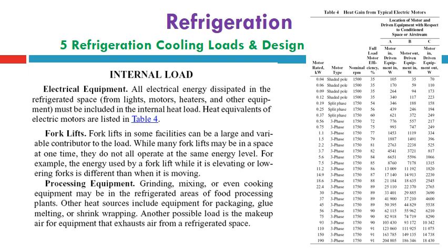Then the second part, forklifts. Forklifts in some facilities can be a large and variable contributor to the load. While many forklifts may be in a space at one time, they don't all operate at the same energy level. For example, the energy used by a forklift while it's elevating or lowering forks is different than when it's moving. So the internal load components should consider the number of forklifts and their capacity, and the heat generated from the engine, especially when using a diesel engine. You should estimate from the manufacturer the amount of heat dissipated by radiation from the diesel engine the forklift is equipped with.